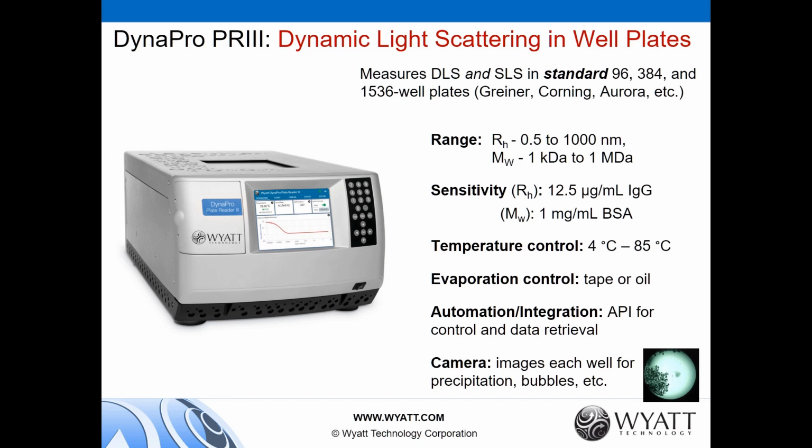The DynaPro offers an API for control of the instrument and data retrieval. So again, if you want to integrate it with your existing plate-based robotics, that will work. And it integrates a camera which images the bottom of each well to look at precipitation, formation of bubbles, whether it's to determine what else is going on in your sample, or to go back and do diagnostics and see why perhaps you got a funny looking autocorrelation function.